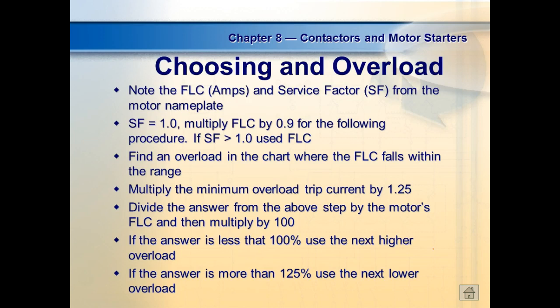The service factor is just a number we use to determine how much we can technically overload that motor without burning it up. If it's got a service factor of one, it means one times the full load current. We're not changing the voltage. Normally we don't consider the voltage, but if I've got a one horsepower motor and I want 1.25 horsepower out of it, it's going to pull 25% more current. To calculate 25% more current, we multiply by 1.25. You understand?